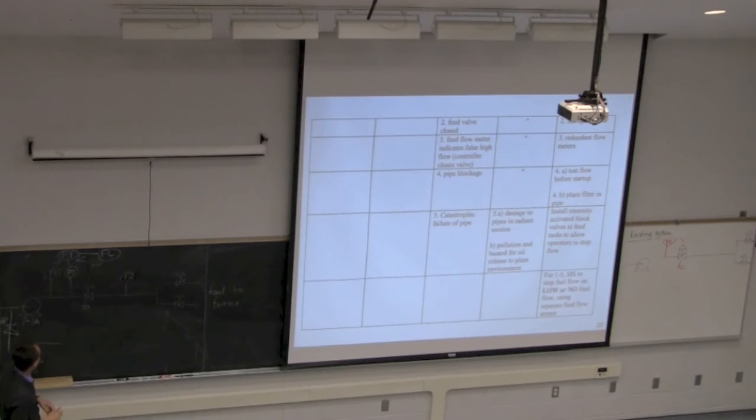Let's take a look at the failure condition. So if F1 fails and reads too high, then F2 is your only reliable reading. Take the lowest of the two, so it's going to take F2 and control the valve. So then essentially you've created a feedback control loop through F2 here. Well, if F2 fails and reads too high, then F1's reading is going to be used. Then we're back to just our original system that we had.